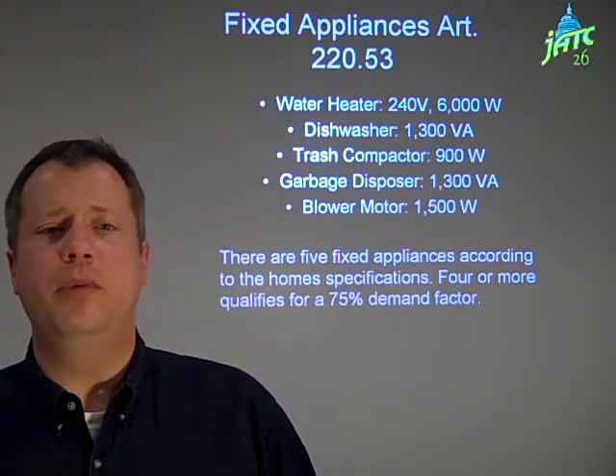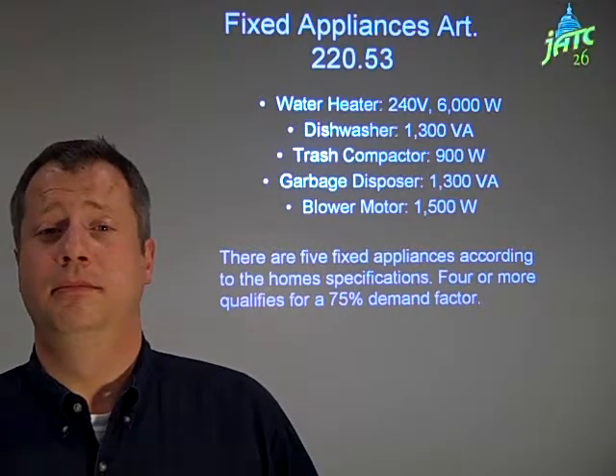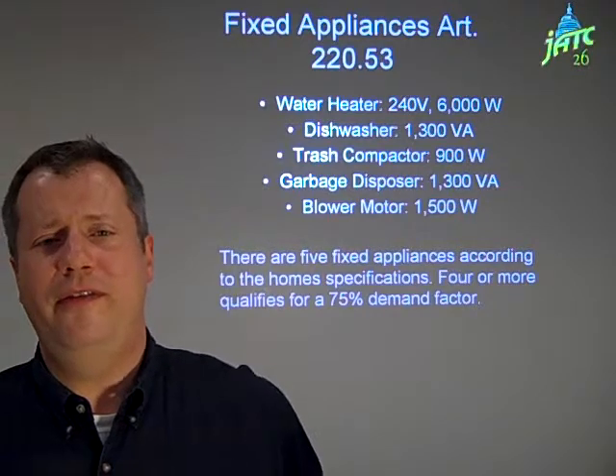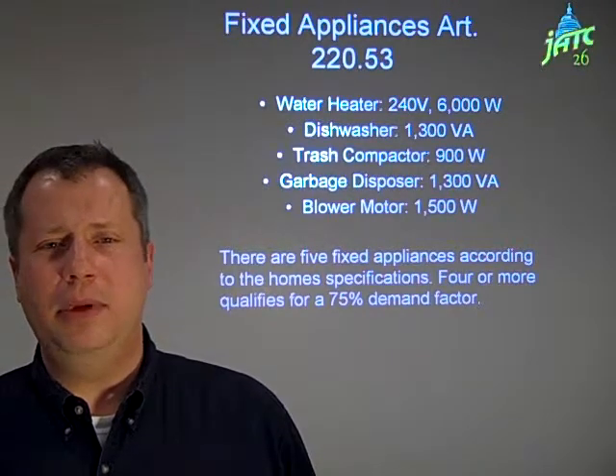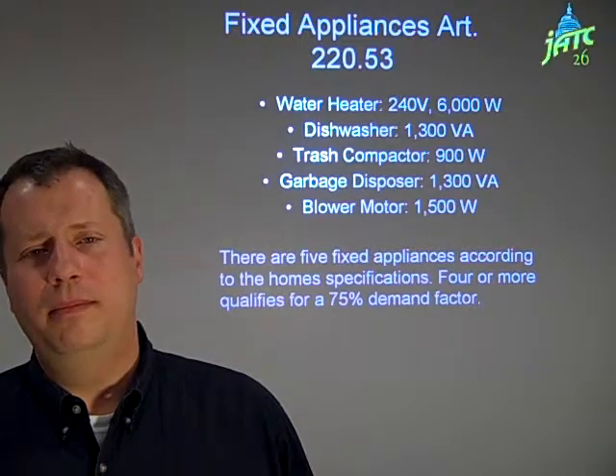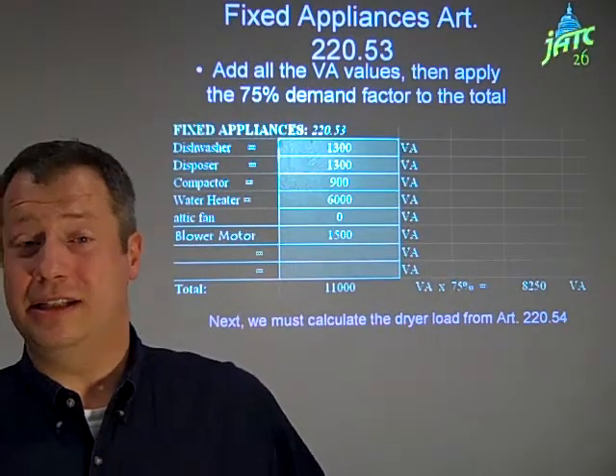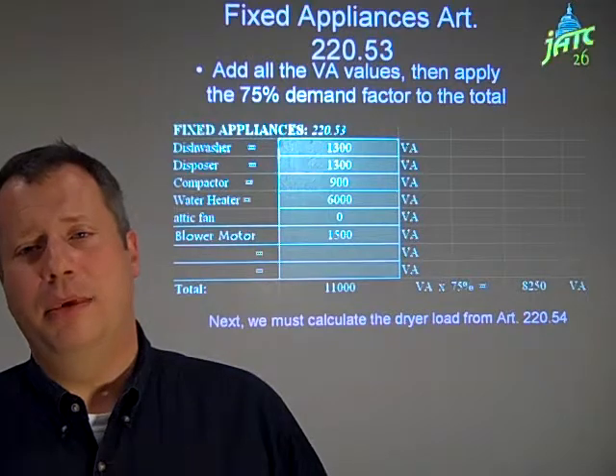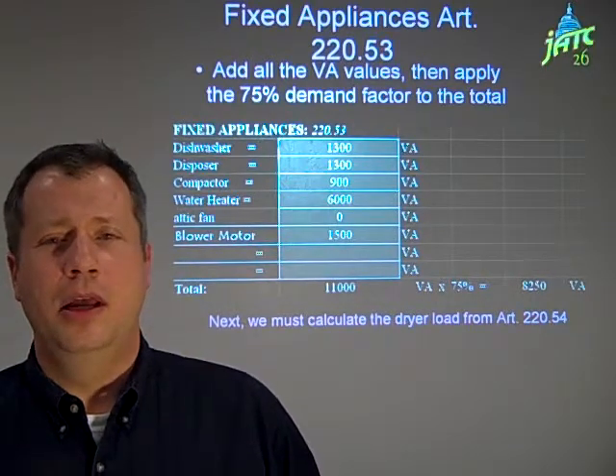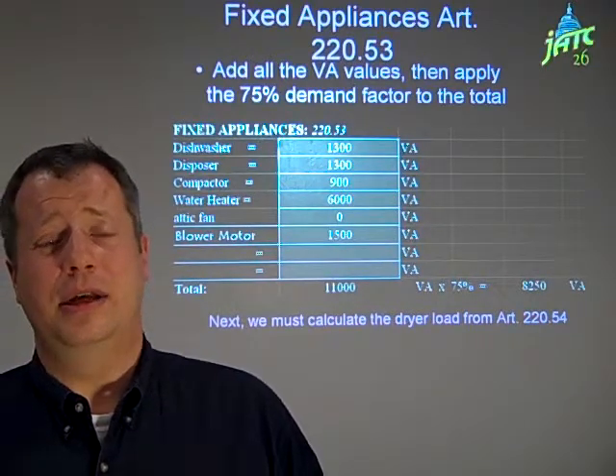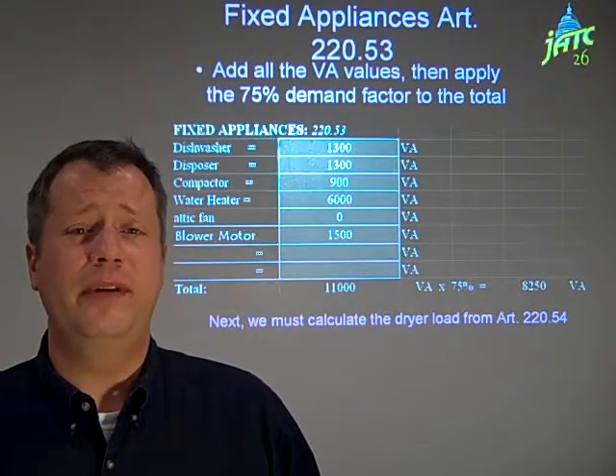That should make some sense — the more loads there are, the less likely it is that they are all on at the same time. Because we have five of them, we can total up all the nameplate ratings and multiply that total — in this case 11,000 volt-amps — by 0.75 or 75%. Our fixed appliances allowance comes out to 8,250 volt-amps. That's the second part.